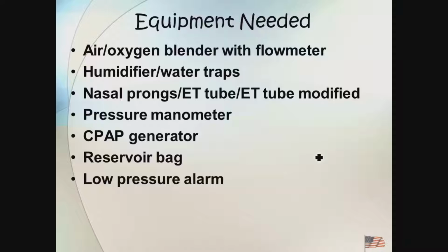And one that I'm going to modify and show you is the nasal prongs. It's probably the most common one that would be utilized. I'm going to have a pressure manometer to monitor how much CPAP I'm applying, because too much is as bad as too little. Some kind of a device to generate the CPAP, and I'll hold off on what I mean by that in a second. A reservoir bag system, which is a little bit different than what you currently have, and perhaps even a low pressure alarm to detect when something's gone wrong with the system.